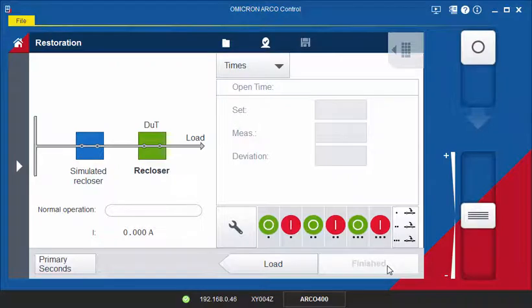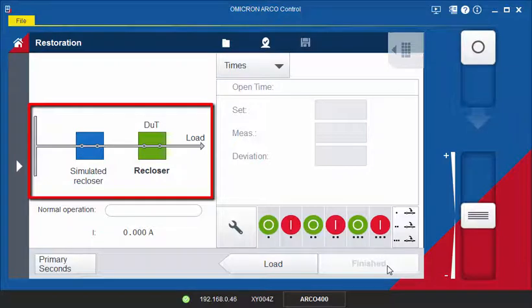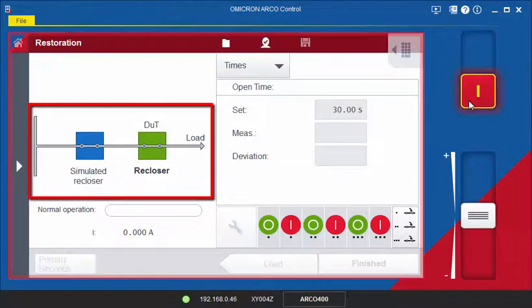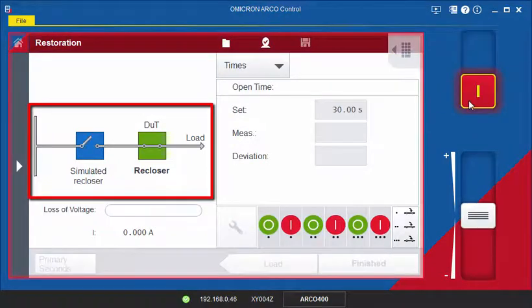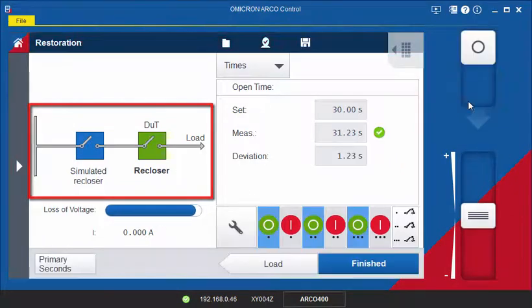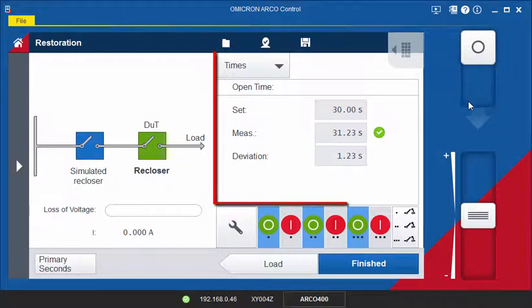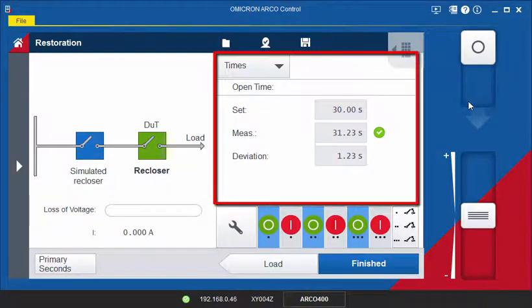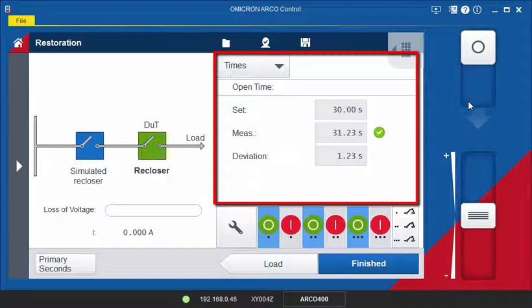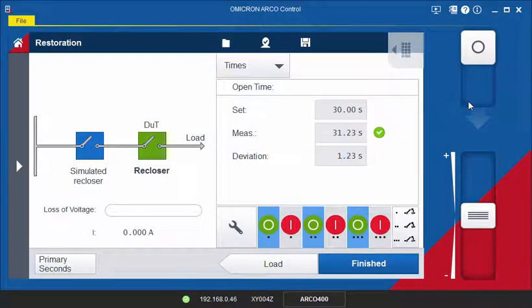On the Test screen, you will see a diagram of your application showing the switching states of the reclosers during the test. In the Times area on the right, you will see the measured Open Time compared to the Open Time setting. If the measured time is within the defined tolerance, the test is assessed OK, which means that the recloser R2 in our example opens within the correct time limit.